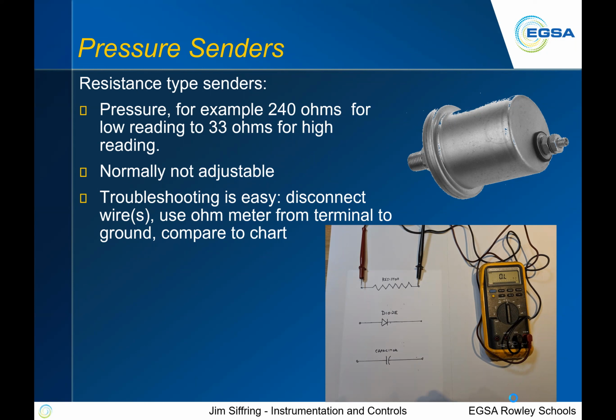So if you're looking at it to look at engine oil pressure or something like that, maybe that device will read 0 to 100 psi or something like that, and you can calibrate that to a gauge, and that gauge will say, okay, at 240 ohms, I'm going to read minimum. At 33 ohms, I'm going to read maximum, and set up your gradients between there. And you've got everything you need there.